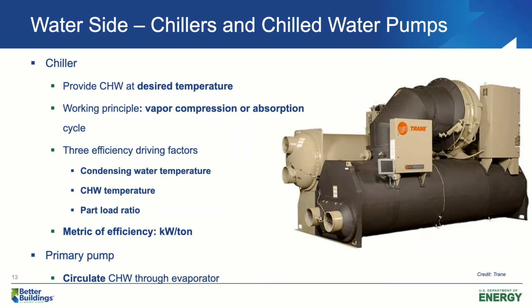We also have primary pumps. The job of primary pumps is to overcome the pressure loss across the evaporators of chillers and to circulate water through evaporators so we can get chilled water.